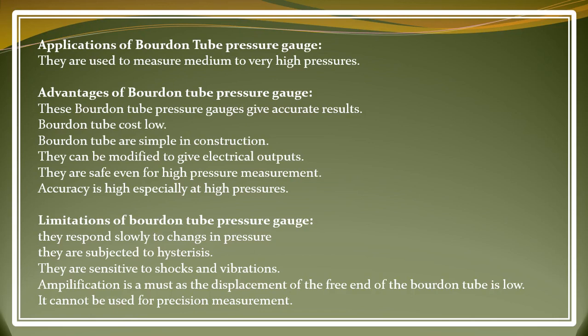So as you can understand, this is a mechanical assembly, so we can convert it to give an output in electrical form. Just add some more mechanical stuff, like you can attach an LVDT, and you can get an electrical output. So they can be modified to give an electrical output. They are safe even for high pressure measurement, because this is a closed mechanical system where, when we apply a pressure, all the pressure is exerted on the Bourdon tube, so it is safe from any hazardous situation.